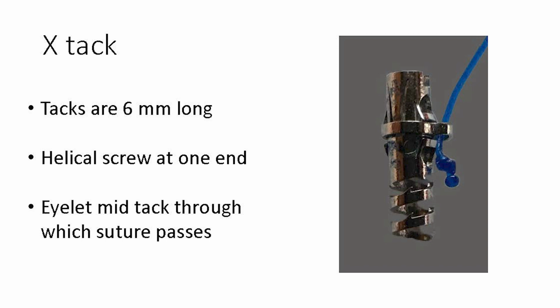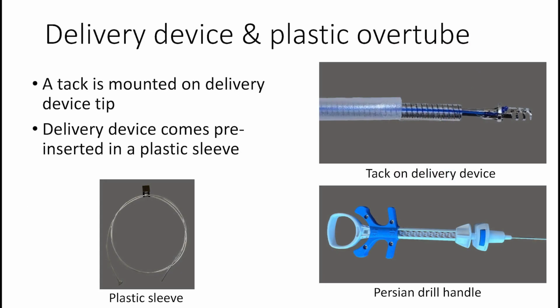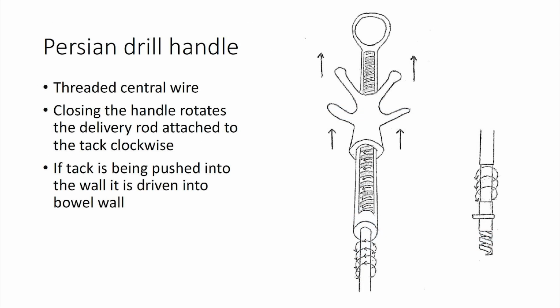The metal tacks are 6 millimeters long and have a threaded helical screw at one end. There is an eyelet mid-tack through which the suture passes. A knot prevents the suture from being pulled out. In addition to the delivery device, there is a plastic sleeve that protects the scope. The delivery device is preloaded with the first tack and comes already inserted through the sleeve. The handle of the delivery device is a Persian drill, which when manually closed rotates the rod attached to the screw. Provided the delivery device is being pushed into the mucosa when the drill handle is closed, the rotation will screw the tack into the wall.